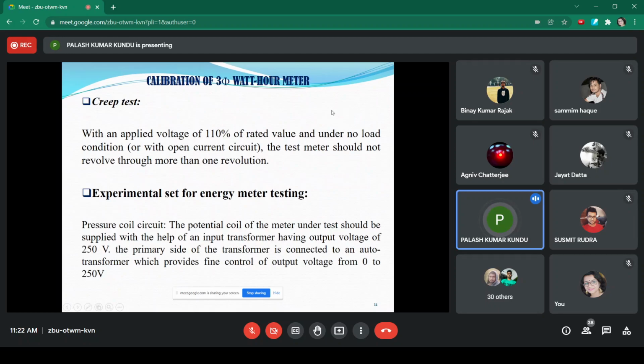The third test is called the test of the energy meter under no load condition. We know when the current coil of the induction disc type energy meter is switched off, that means no load current is flowing. So what will happen? No driving torque theoretically will develop. But due to the overcompensations, the different compensation methods, that means lag adjustment and like that.